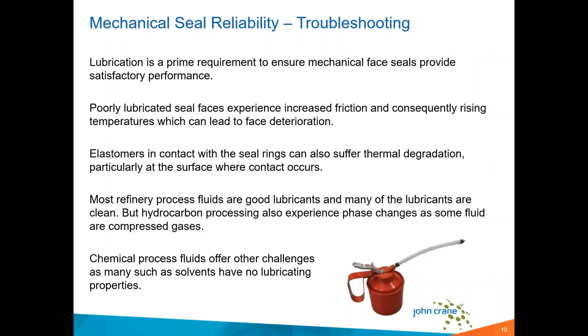This is critical because we talk about volatile hydrocarbons and hydrocarbon processing, and you have to contain the phase change in some fluid. Two things happen at seal faces. We have pressure drop and temperatures increasing, and both of those conditions are ripe for increasing phase change.